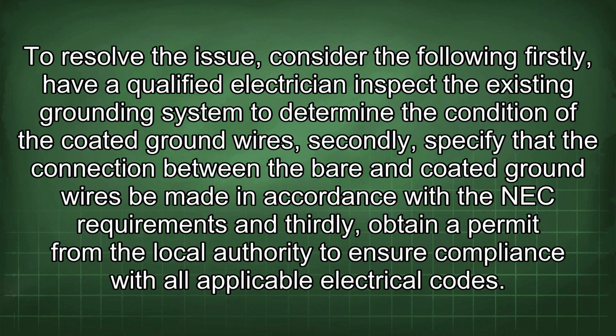Firstly, have a qualified electrician inspect the existing grounding system to determine the condition of the coated ground wires. Secondly, specify that the connection between the bare and coated ground wires be made in accordance with the NEC requirements. And thirdly, obtain a permit from the local authority to ensure compliance with all applicable electrical codes.